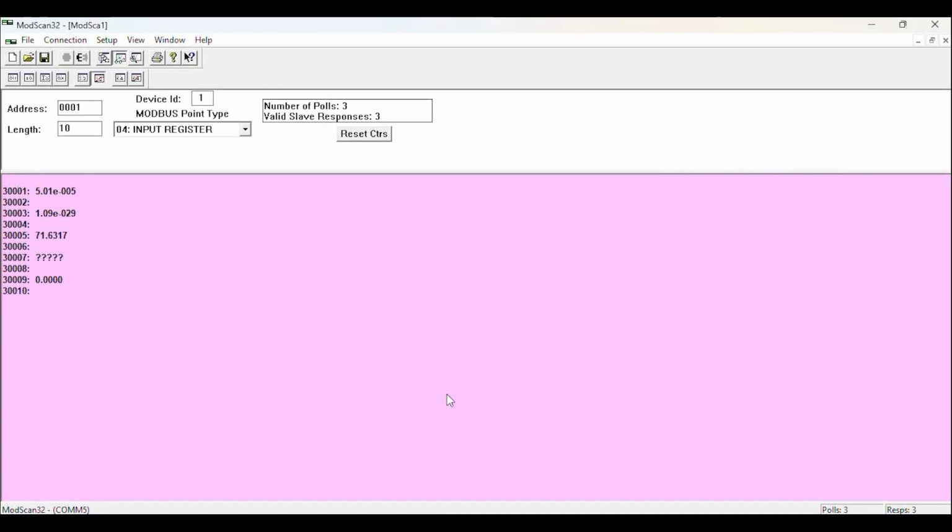If the value appears incorrect, such as an extremely large number, a very small number, or an unrealistic reading, it usually indicates a byte order or word order mismatch. Let's see how to verify the current Endianness setting and change it.